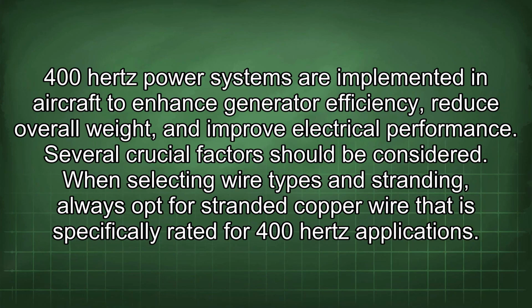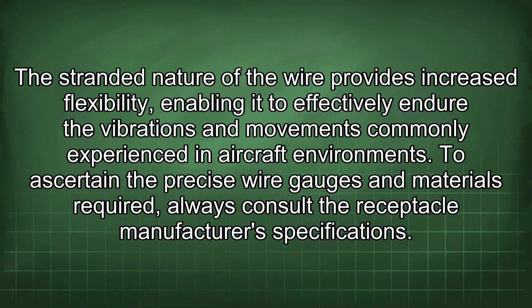400 Hz power systems are implemented in aircraft to enhance generator efficiency, reduce overall weight, and improve electrical performance. Several crucial factors should be considered. When selecting wire types and stranding, always opt for stranded copper wire that is specifically rated for 400 Hz applications. The stranded nature of the wire provides increased flexibility, enabling it to effectively endure the vibrations and movements commonly experienced in aircraft environments. To ascertain the precise wire gauges and materials required, always consult the receptacle manufacturer's specifications.